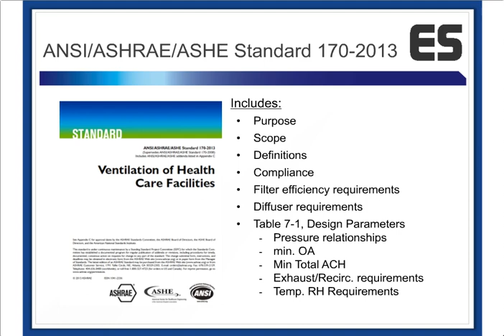And particularly, there's a table used that talks about the pressurization we require, what the air changes should be, the total air changes, temperature and humidity requirements, etc. This is the document that's really the foundation for those design elements in a hospital.